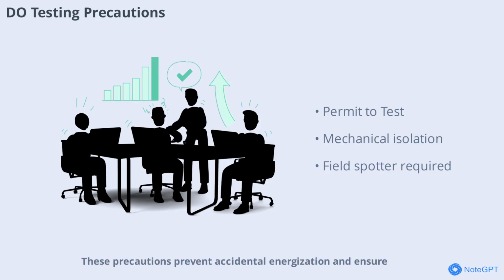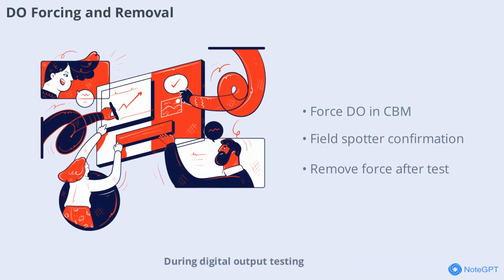These precautions prevent accidental energization and ensure that testing is conducted safely and responsibly. During digital output testing, the control room engineer forces the DO variable to true in CBM. The field spotter confirms the device energizes and the engineer removes the force afterward. This ensures that outputs are mapped correctly and prevents unintended operations.